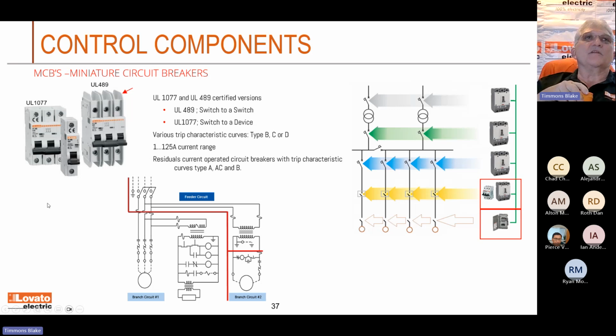Now we're talking about miniature circuit breakers. You have the two different ratings, the UL 1077 and UL 489. 489 is going to be that feeder circuit from a switch to a switch. The 1077 will be a switch to a device. And usually you can tell this by looking at the fins. See, I got that red arrow at the top. Those 489 breakers will typically have those fins on it. And basically, I think we just wanted to see some spacing between the two terminals. So you put them fins on there and we're all good.